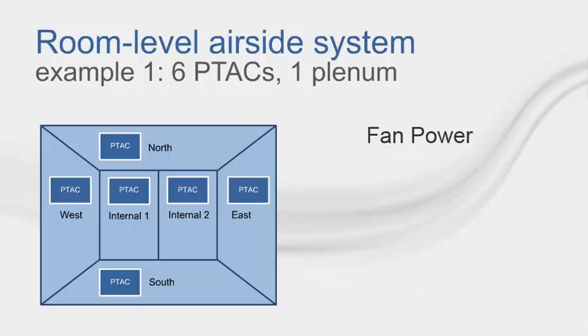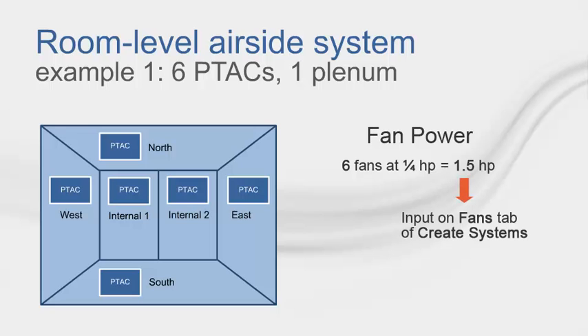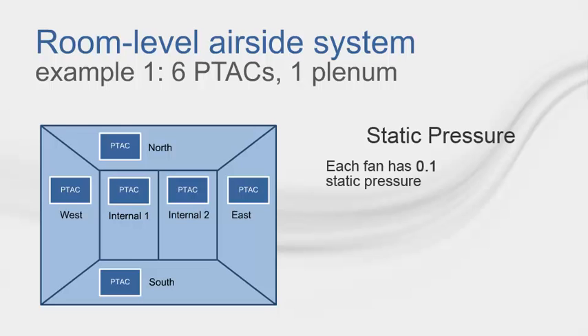Here is another modeling tip regarding fan information. Pretend you take the six room building model and each room gets a PTAC unit, all the same size, which means you only have one system. To correctly model this on the fans tab, you should add up the fan powers. If each PTAC has a quarter horsepower fan and there are six fans, then the horsepower you would input would be one quarter times six, which is 1.5 horsepower. The static pressure is a little different — if each fan sees 0.1 inch of static, then you would only enter 0.1 inches of static.